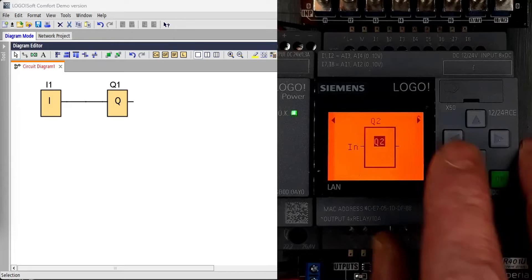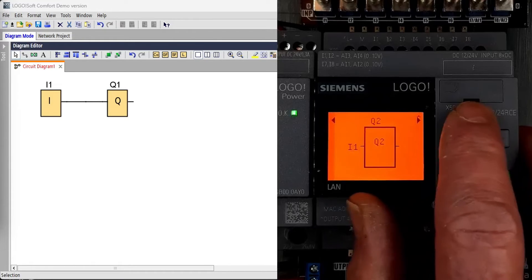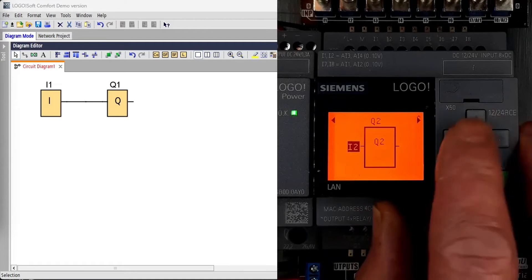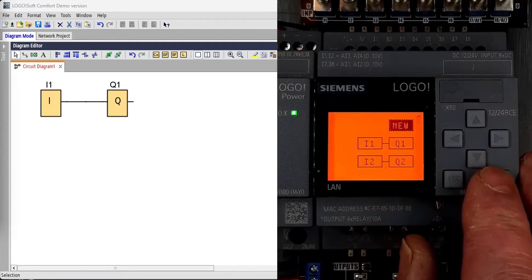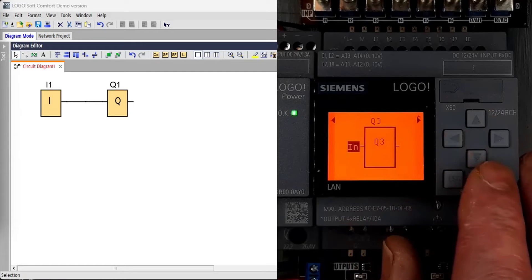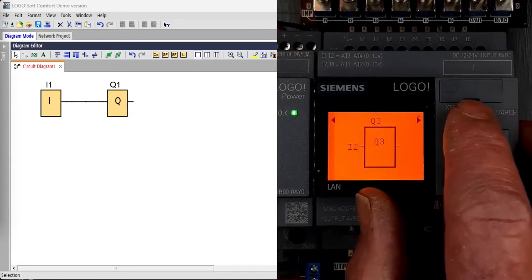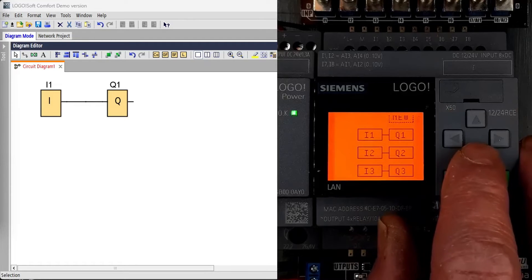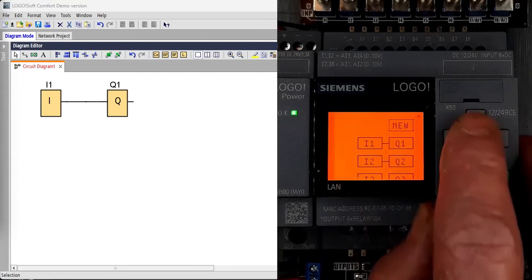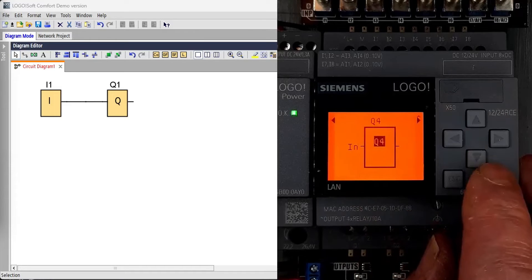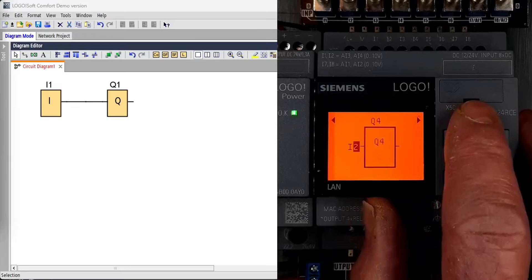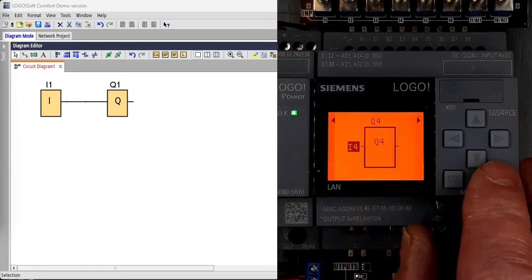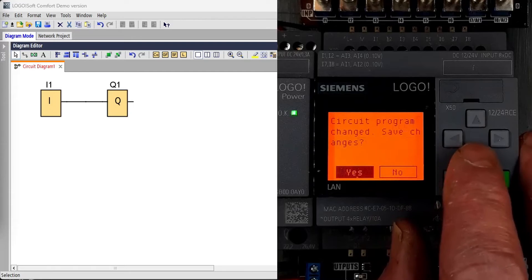Here I'm putting input 1, toggling output 1, input 2, output 2, etc. Note that programming from the front panel always works from the output backwards. So you start with Q4, go to the input type you want. It could be a function block, but in this case it's just an input.